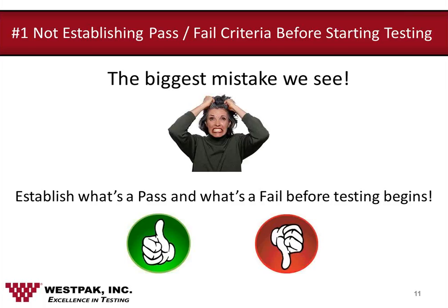And then they get to the end of the test and they ask us, well, did it pass or did it fail? And we go back and say, well, did you have criteria for your pass-fail before you started testing? And they go, no. And so then they go back, and it's a lot of meetings at time and screaming and yelling back at their company trying to figure out, did this thing pass or fail? So what you want to do is you want to establish the pass-fail criteria prior to the start of testing.